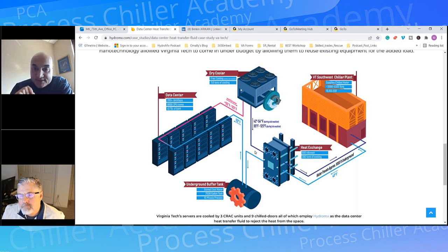What that means is that under stress, which is more pressure - I love to give the Empire State example, which I'm seeing from my office. They have 26-inch risers going up 100 floors. That same fluid you're pumping, at the end of the day, is going through a half-inch pipe on the coils. That's the definition of stress in the fluid.